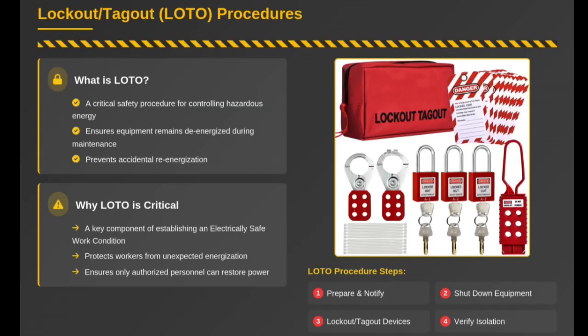Lockout/tagout, or LOTO, is one of the most critical safety procedures in NFPA 70E. It prevents accidental energization during maintenance or repair. The basic steps are: first, prepare and notify all affected employees. Second, shut down the equipment. Third, apply lockout/tagout devices. And finally, verify that the equipment is completely isolated. LOTO saves lives every single time it's used properly.